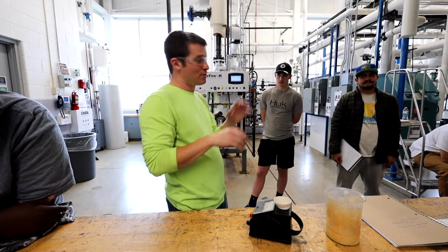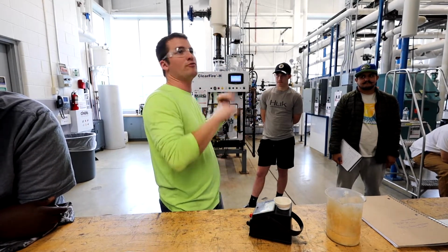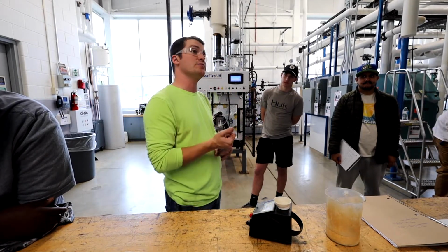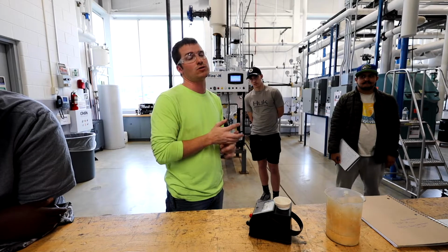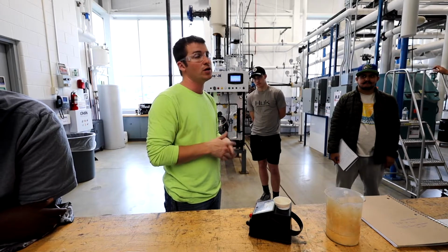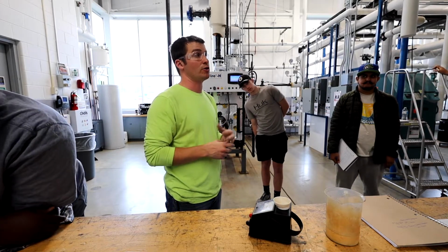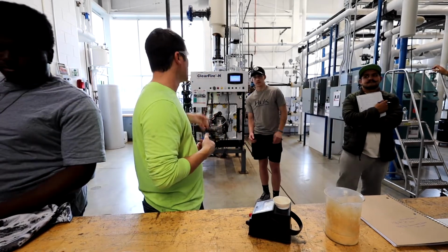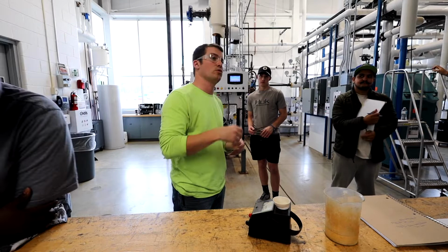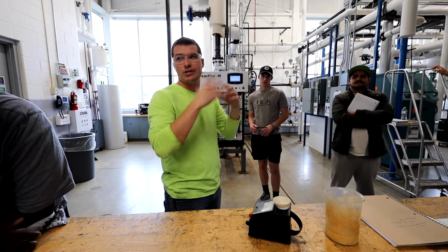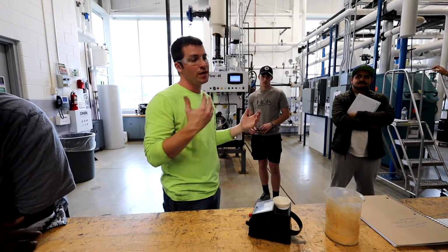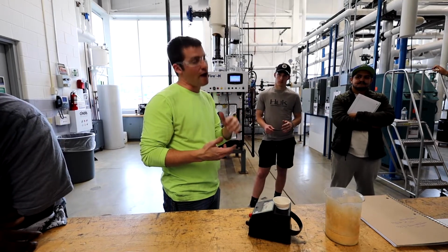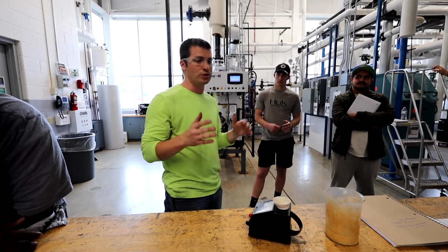Now, that doesn't mean you can just close the valves and never ever drain water out of your system and run your conductivity to 20,000, right? So ASME has guidelines. We can't exceed 7,000 conductivity in a boiler, and we're not supposed to exceed 700 total alkalinity in a boiler. And the reason being is at those levels, you run the risk of having boiler water carryover where water actually is going to leave the boiler and not just dry steam. And the potential for scaling it up, fouling it, everything increases the higher we run it. So there's a trade-off, right?